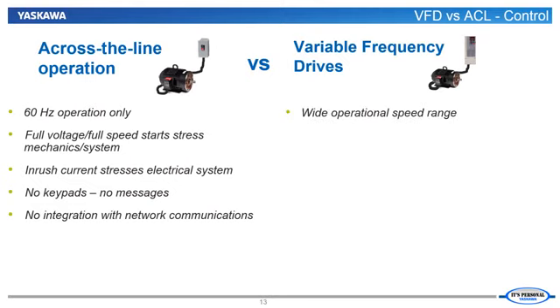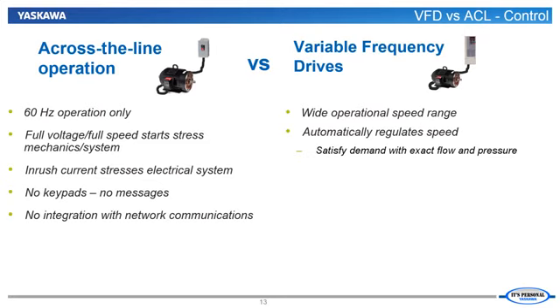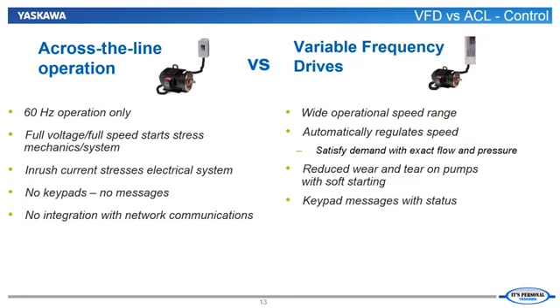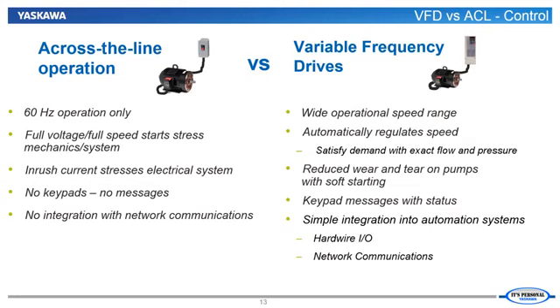Conversely, the VFD runs only as fast as is necessary and can self-regulate to match the system's flow or pressure needs. The VFD will soft start the fan or pump, which eliminates inrush current levels and is far less stressful on the mechanical portions of the installation, like fan belting and pump valves, which in turn lengthens their lifespans. A VFD has the ability through its keypad to give real-time information on everything from the speed to the pressure to the amp draw of the motor. This information provides peace of mind to the person in charge of making sure the pump or fan is performing optimally. Lastly, a VFD can easily be integrated into an automation network via option boards or hardwired I/O. Most data acquisition is a cinch when the VFD can report details of its status in real time over the network.